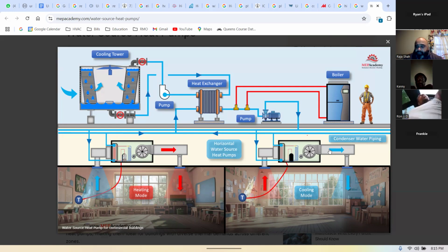But now peep game though, the air is flowing this way. So this right here, look where my compressor is going. The suction line goes into my compressor. You with me, Ron? Yes, sir. You see this coil? That's my evaporator coil. The suction line is going into my compressor. It comes out my discharge line, the outlet, and then it's going into this coil.